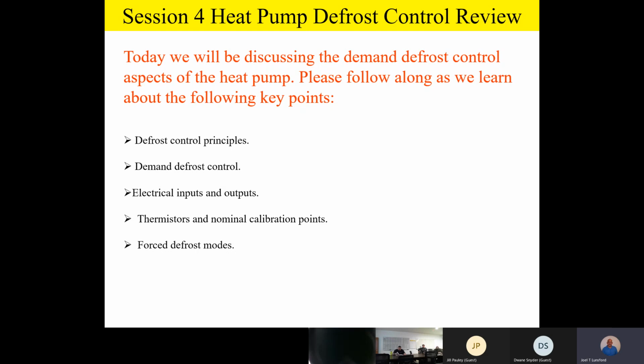So today we're going to talk a little bit about demand defrost controls again, but we're also going to cover defrost control principles. We're going to quickly overview the difference between a demand defrost control and a time temperature control. In addition, we're going to talk about the electrical inputs and outputs of the demand defrost control, as well as thermistors and nominal calibration points, and then of course forced defrost modes for servicing.